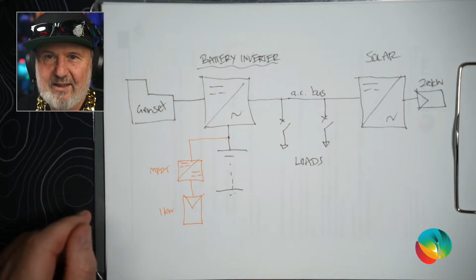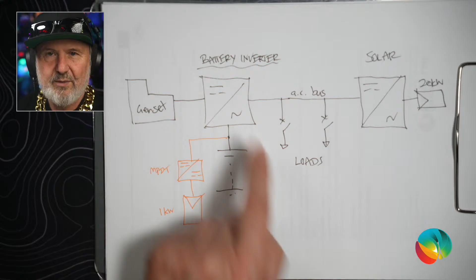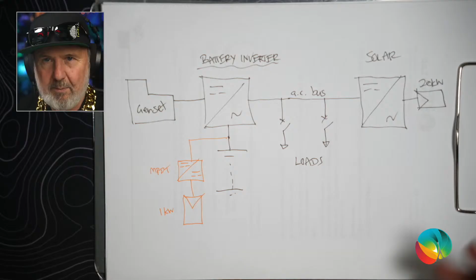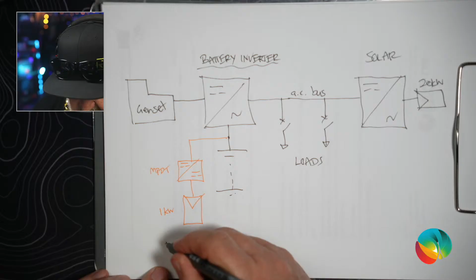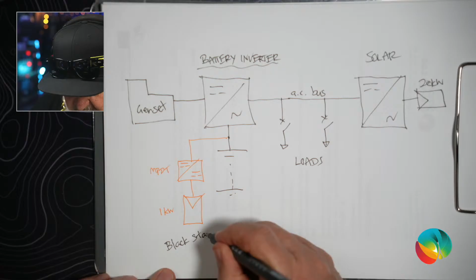But this little one here, putting in just a small amount of power, is going to raise the battery voltage just enough to wake up the battery inverter. And so the battery inverter wakes up and creates an AC supply at this point here. The solar inverter sees that there is a grid to parallel with, and it powers up, and you're back in action again. So this is your black start protection system. Now, particularly when you're off grid and help is a long way away, this is a very nice solution.